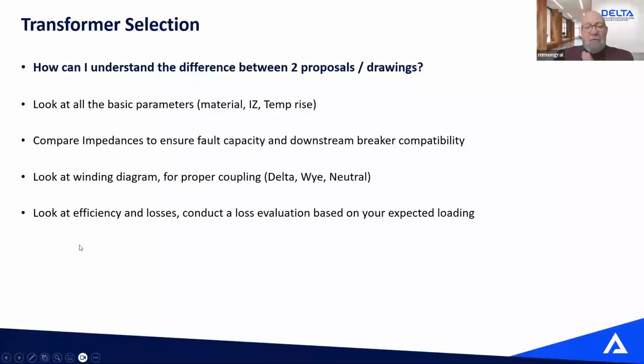And as a customer, as a consultant, how can I understand those differences? If you have two drawings or two proposals from two different manufacturers, well, look at the drawing or the spec sheet and look at all the basic parameters like the material, the temperature rise, the impedance. Compare your impedances to ensure that the fault capacity on your breaker is compatible. You may have a more cost-efficient transformer, but you may have to change your breaker for a higher kA rating, so you won't save much in those cases.